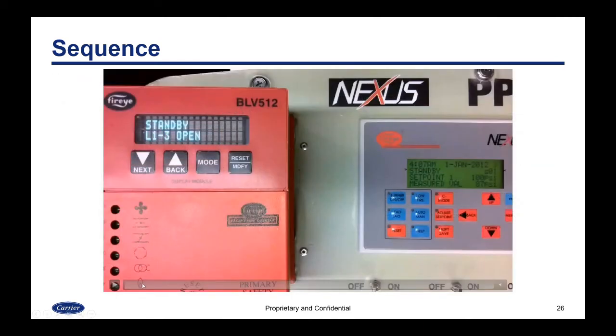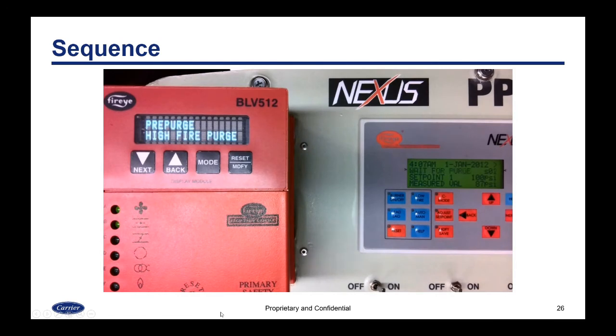So here's a video showing that sequence. Let me play that. You can see both devices. Right now it's moving to the purge position. When it gets to the purge position, you'll see the PPC display switch to saying purge, and you'll see the burner logic start to count down the purge. So it says purge. It's counting down the pre-purge. When it's done counting down the pre-purge, it's going to issue the command to drive to the ignition position.